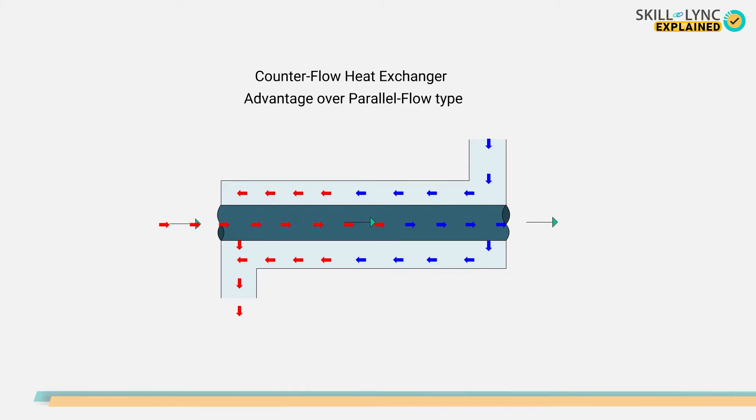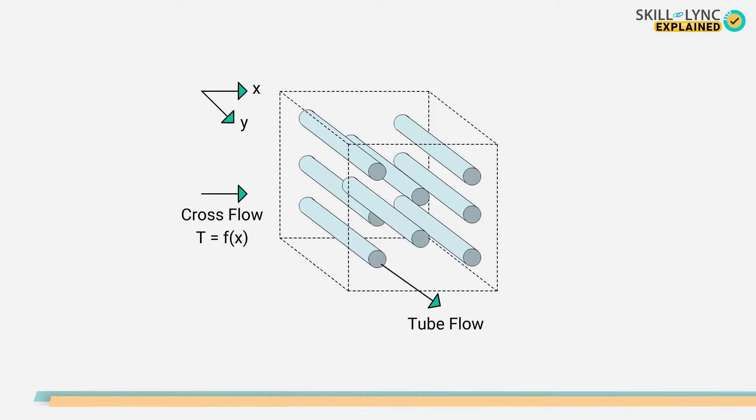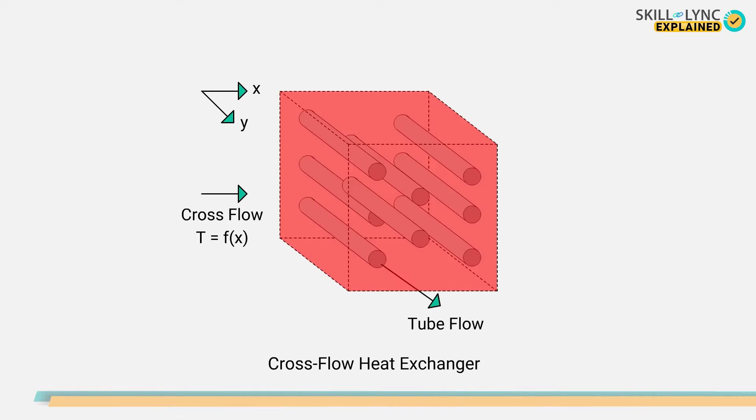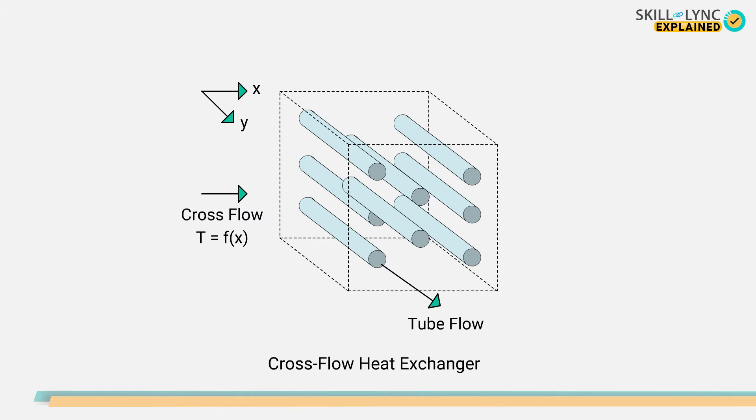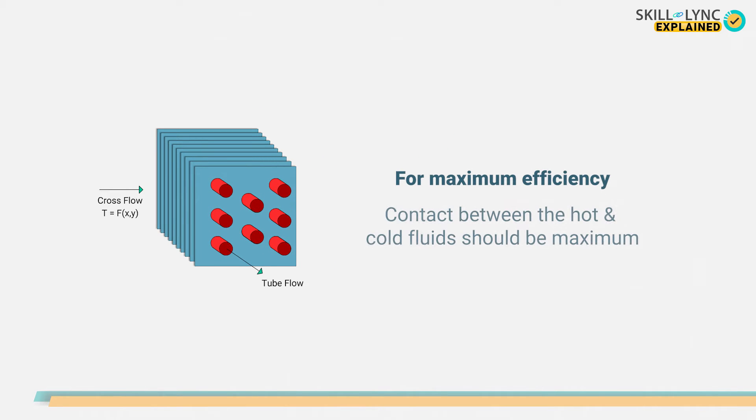Counter flow heat exchangers have one advantage over parallel flow type—that being the average temperature difference is higher, thus resulting in much more efficient heat transfer. The third type has the fluid flow in a perpendicular direction to each other. This type is called the cross flow heat exchanger. In such types, the flow of one fluid is in the x direction while the other fluid flows in the y direction. This type of heat exchanger can have fins to facilitate the flow in one direction while the tubes carry the other fluid.